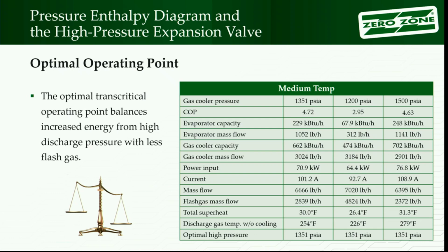So the evaporator mass flow then follows that. Evaporator capacity kind of takes a chunk with that. Gas cooler goes up a little bit, right? Lower pressure, I get a little more efficiency out of my compressors, can pump a little more gas through the compressor, I have a little bit higher mass flow in here. Same thing happens when I get up to 1500, I'm going in the other direction, not quite as much mass flow through that. Power moves around as we expect. Lower discharge pressures, lower power consumption, higher discharge pressures, higher power consumption. And then of course current goes around with that.